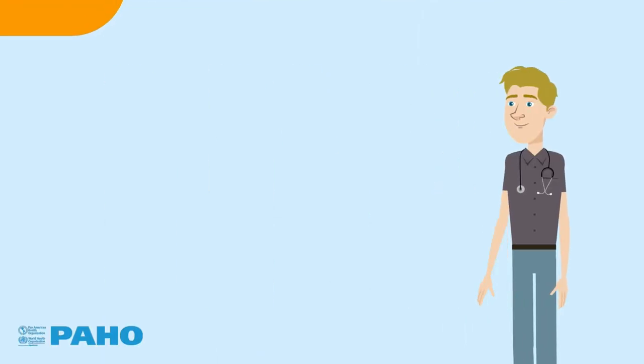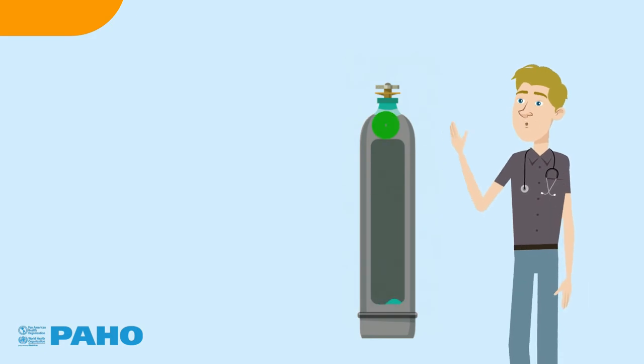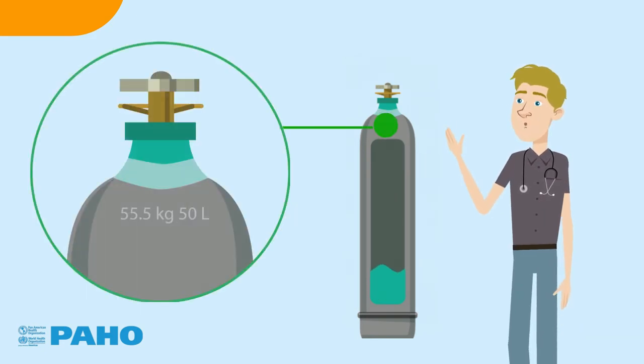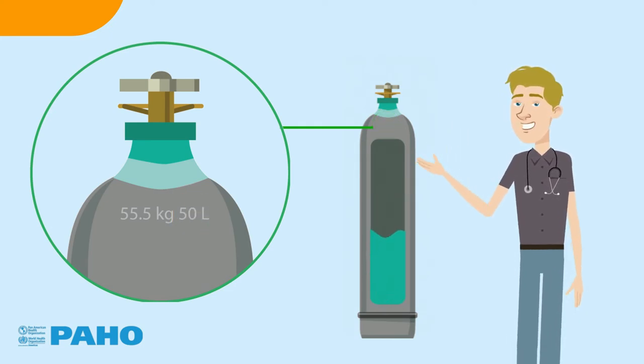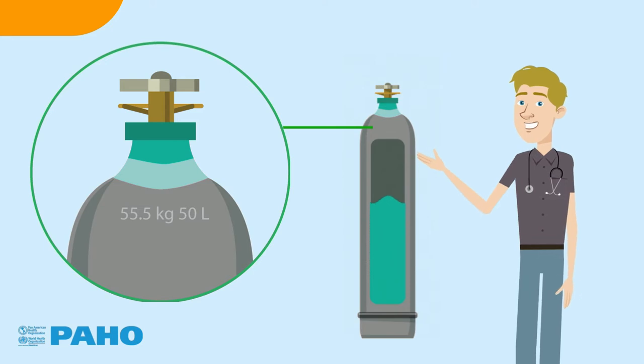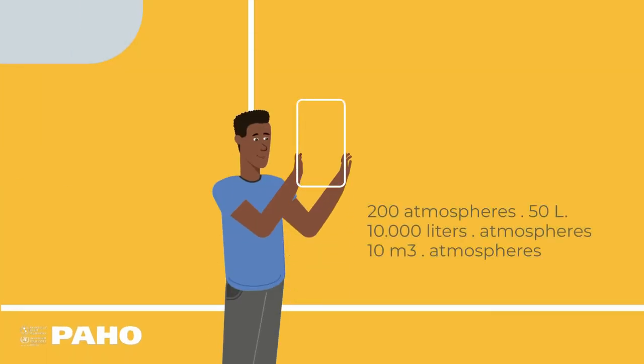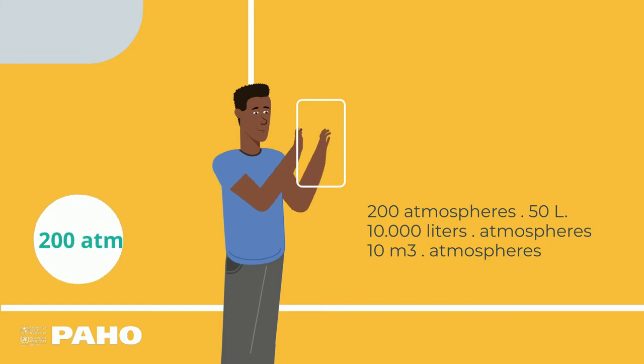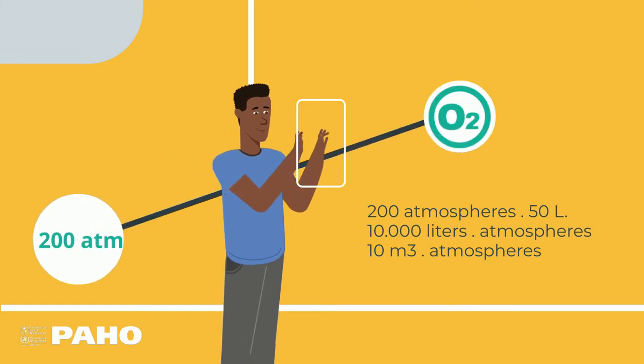Another important piece of information is the internal volume of the cylinder, which is equivalent to the volume of water that it can contain. This amount is usually expressed in liters and is written on the body of the cylinder. Combined with the internal pressure, you can use it to calculate the amount of oxygen that can be stored in the cylinder.